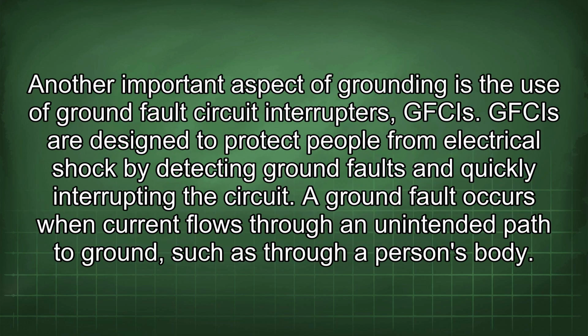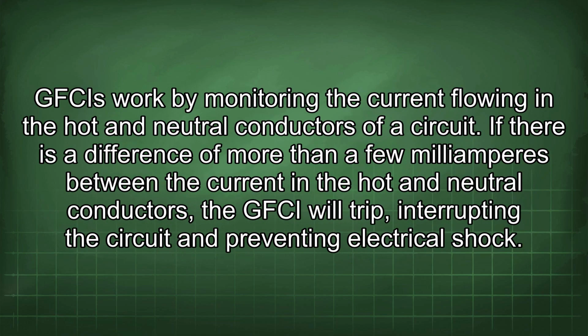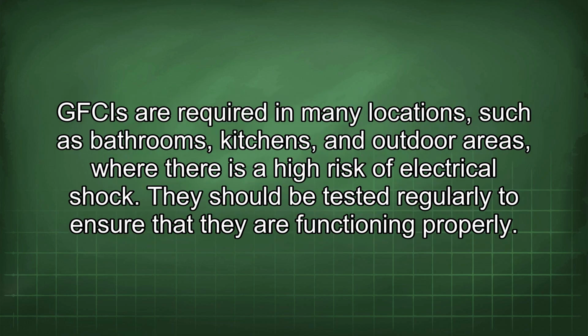Another important aspect of grounding is the use of ground fault circuit interrupters, GFCIs. GFCIs are designed to protect people from electrical shock by detecting ground faults and quickly interrupting the circuit. A ground fault occurs when current flows through an unintended path to ground, such as through a person's body. GFCIs work by monitoring the current flowing in the hot and neutral conductors of a circuit. If there is a difference of more than a few milliamperes between the current in the hot and neutral conductors, the GFCI will trip, interrupting the circuit and preventing electrical shock. GFCIs are required in many locations, such as bathrooms, kitchens, and outdoor areas, where there is a high risk of electrical shock. They should be tested regularly to ensure that they are functioning properly.